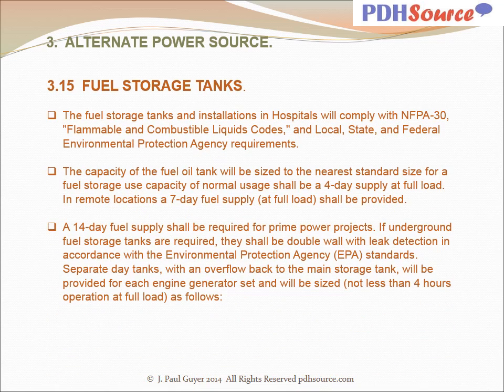The fuel storage tanks and installations in hospitals will comply with NFPA 30 Flammable and Combustible Liquids Code and applicable local, state, and federal environmental requirements and safety requirements. The capacity of the fuel oil tank will be sized to the nearest standard size for a fuel storage use capacity of normal usage, which shall be a 4-day supply at full load. In remote locations, a 7-day fuel supply at full load shall be provided. A 14-day fuel supply shall be required for prime power projects. If underground fuel storage tanks are required, they shall be double wall with leak detection in accordance with EPA standards.